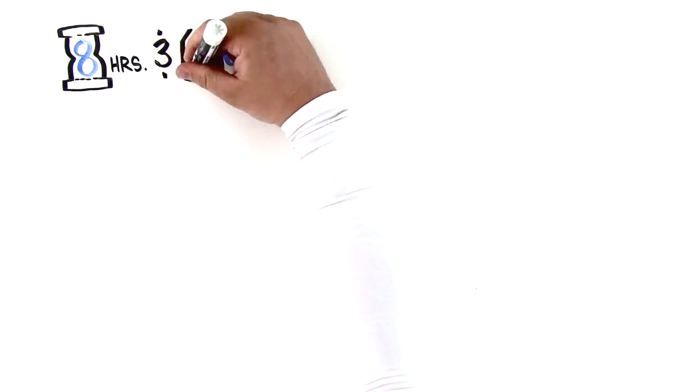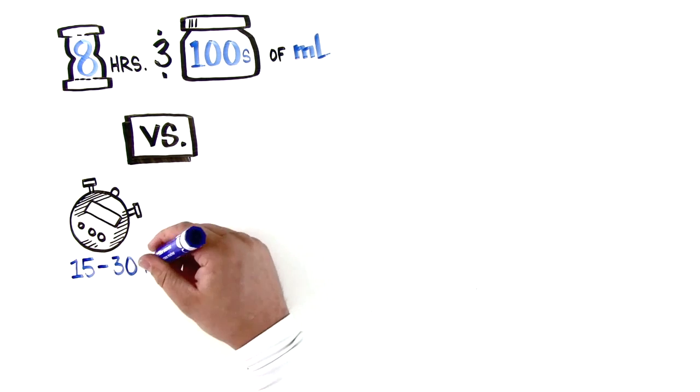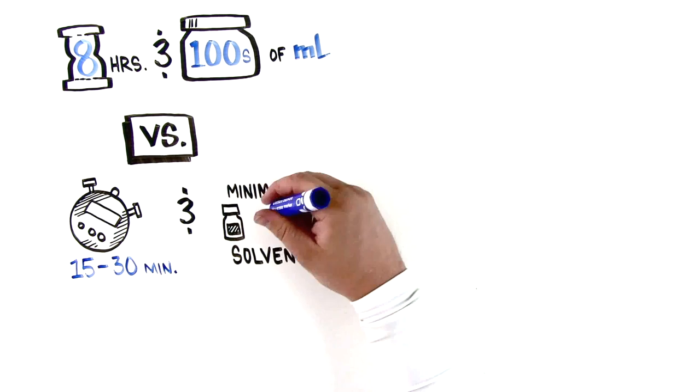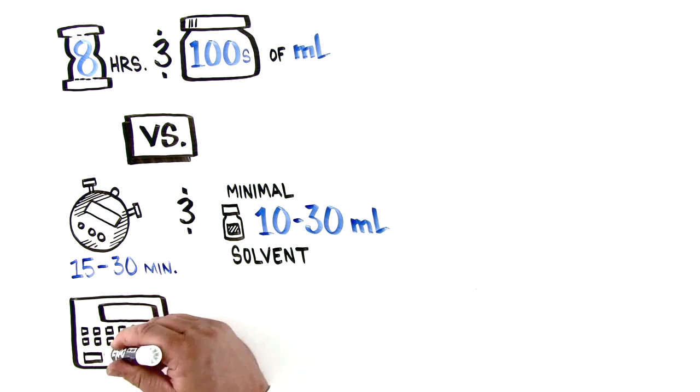While other methods take up to 8 hours and use hundreds of milliliters or more of solvent, the accelerated solvent extraction technique takes 15 to 30 minutes and requires minimal solvent, typically 10 to 30 milliliters, depending on the application. Because it is automated, reproducibility is improved over traditional methods.